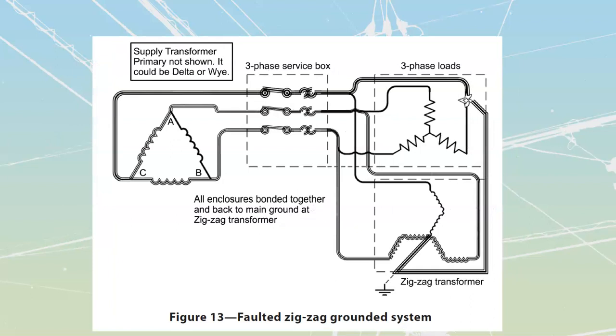So over here, we are going to fault one of our lines. We're going to fault this line right up top over here, which is going to be my C line. So my C line is going to fault over to ground. So I'm going to have a large amount of current that is going to be delivered from C through my fuses over here, and it is going to travel up to here.